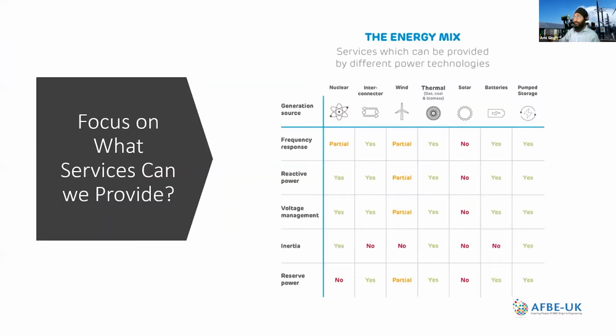In terms of thermal energy, we provide frequency response from Peterhead Power Station. We provide a lot of reactive power and voltage management, largely supporting reactive power. Inertia is quite a large thing for us, considering we are one of the largest generators in northeast Scotland, so we provide a lot of stability to the grid in terms of inertia. We also provide reserve power that's inherent in our generation at the station.